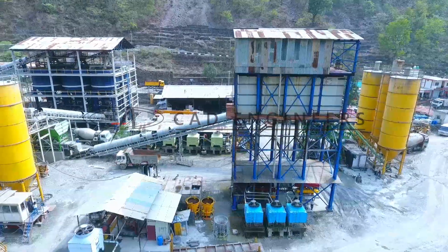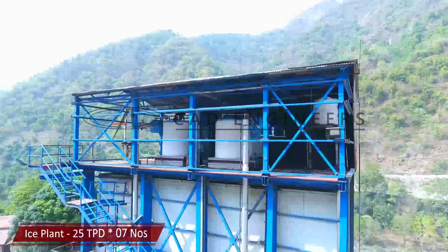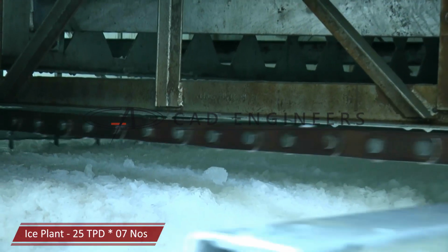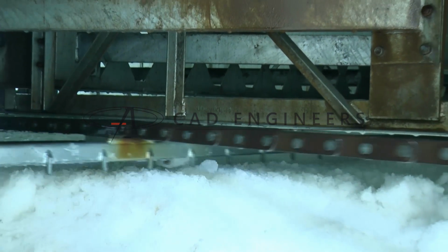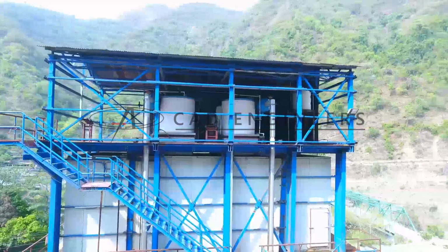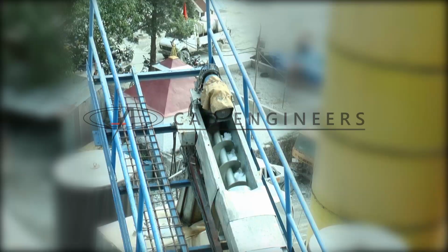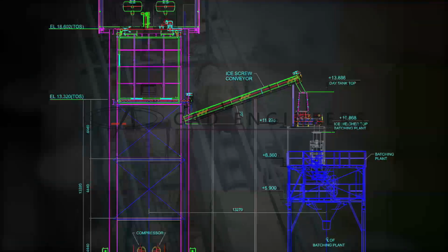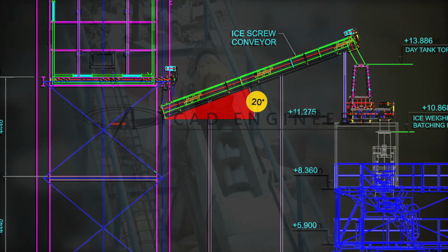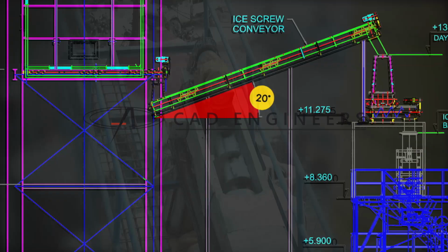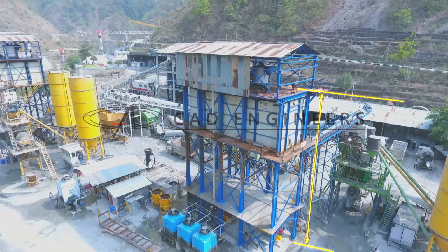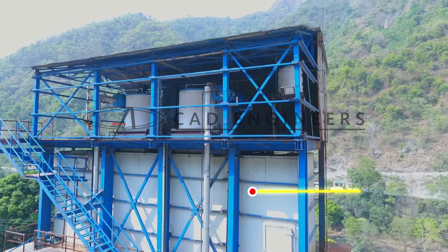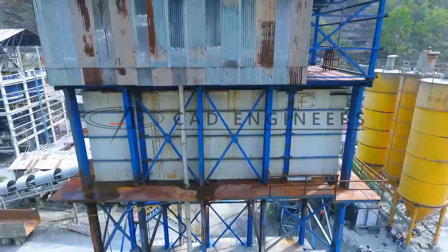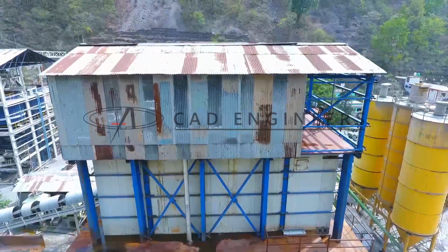For this purpose, 7 ice flake plants of 25 TPD capacity each, and an ice handling system with day tank and metering device are used. The elevation of the ice maker and ice storage room is maintained in such a way that the angle of the ice screw conveyor does not exceed its permissible limits. The ice maker is installed at a height of 17 meters above ground level. Right below, there is an ice storage room of 150 ton capacity. This tower type installation of the ice maker helps to achieve smooth handling of ice flakes.